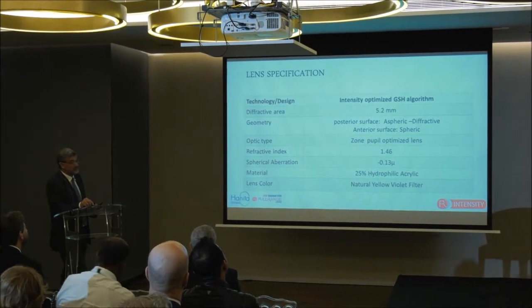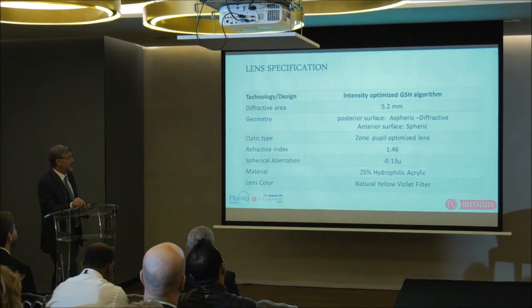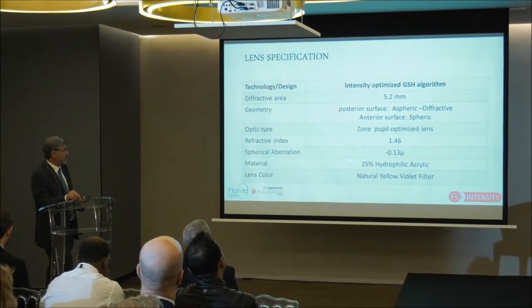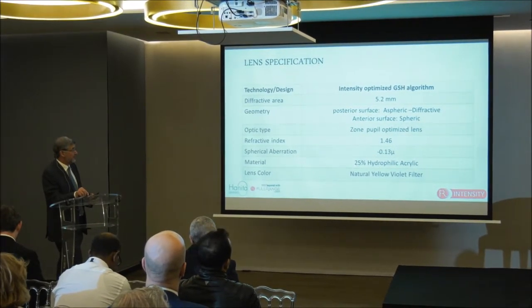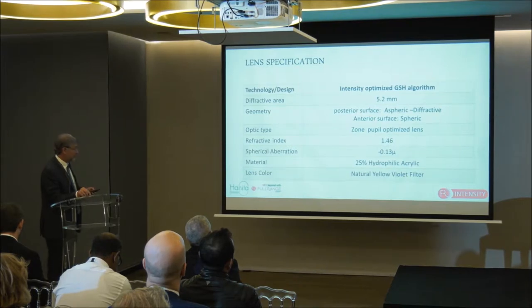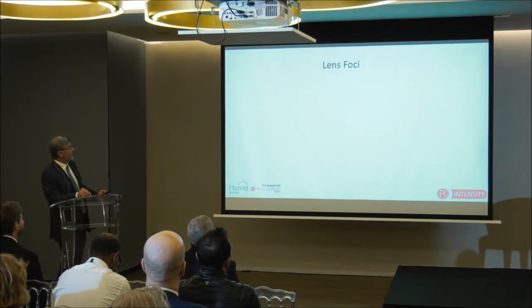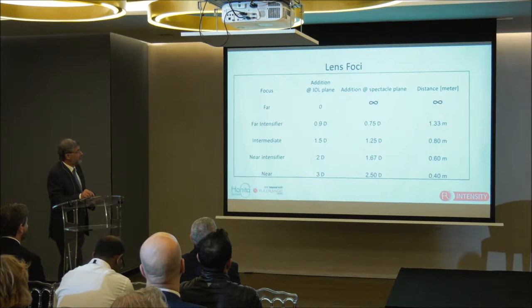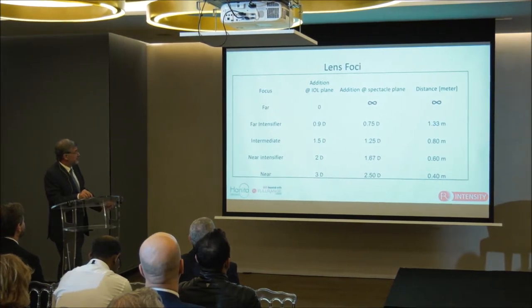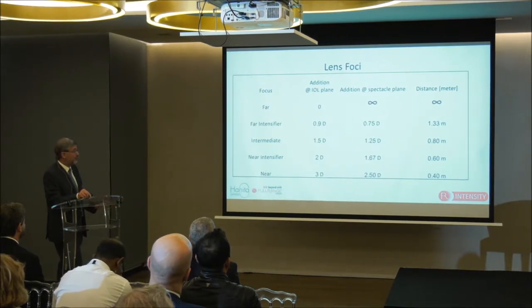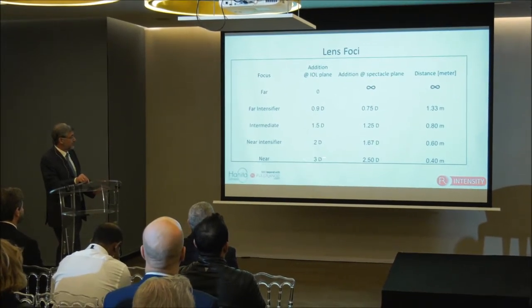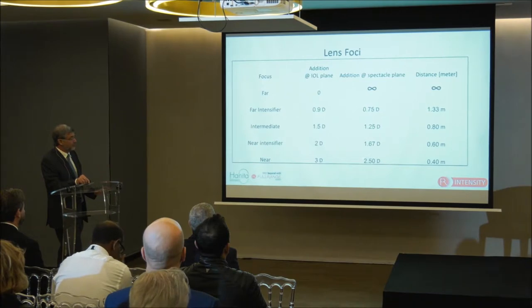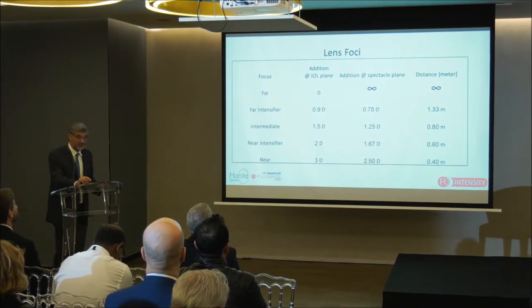This lens has a diffractive area which is quite large — 5.2mm. The diffractive structure is on the posterior surface; the anterior surface is spheric. It is a pupil-optimized lens with a spherical aberration of minus 0.13 microns, a 25% hydrophilic lens, and it also has a natural yellow blue-light blocker. The classical trifocal foci are: zero IOL power providing far focus at infinity; intermediate at 1.5 diopters in the IOL plane (1.25 at spectacle plane), which is about 80 centimeters; and a near focus at 3 diopters IOL plane (2.5 spectacle plane), about 40 centimeters.